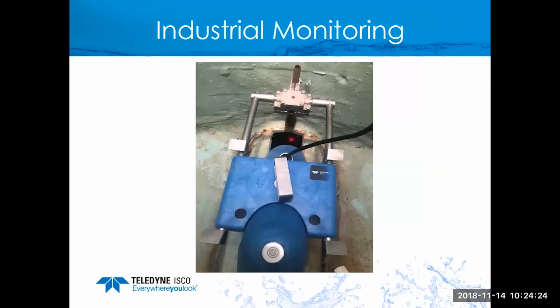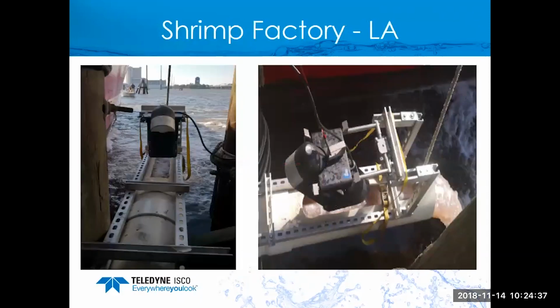By comparison, the other option would have been to dig that whole thing up and try to put a flume in there, which was not going to be an easy solution. So the laser made it very, very easy for them to adapt and get higher accuracy than even with the flume. Here's another one. This is a shrimp facility down south, and they're trying to measure flow here. There was no good solution to doing this. They went ahead with the laser, and you'll notice the cut in the top, just a simple cut in the top of that PVC pipe, and away they go.